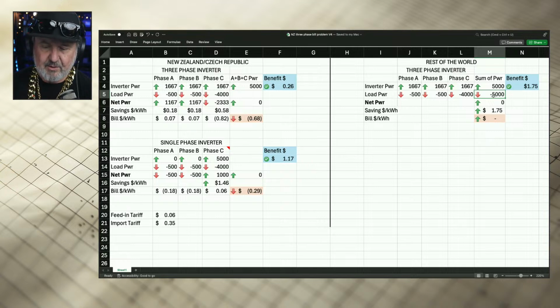Ray says, correct me if I'm wrong, but does the 5% difference between phases restriction also apply to New Zealand, the same as in Aussie? I'll get onto that, Ray, if I have time. That's about the requirement for when you need balanced generation. It really kicks in at larger capacities, so over 5 kVA per phase. So you can be out of balance below that. So in this case, not a problem, putting 5 kilowatts on one phase.